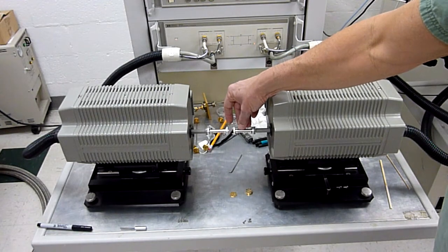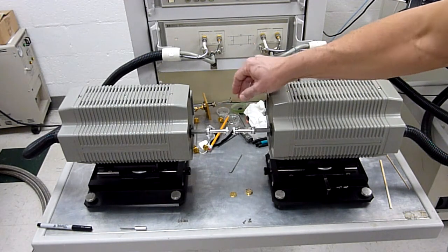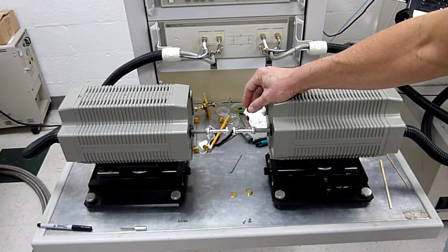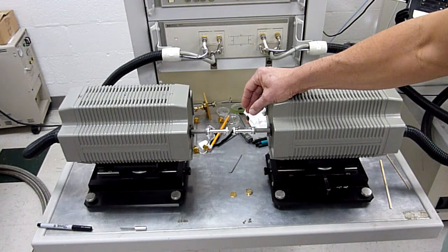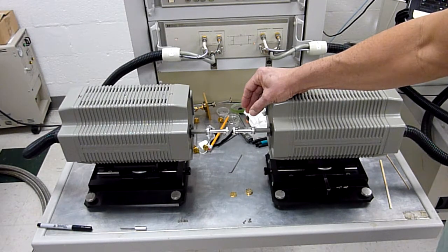And inspect them under a microscope to see what their actual condition is. It could make a world of a difference for your calibration and the measurement you can do.